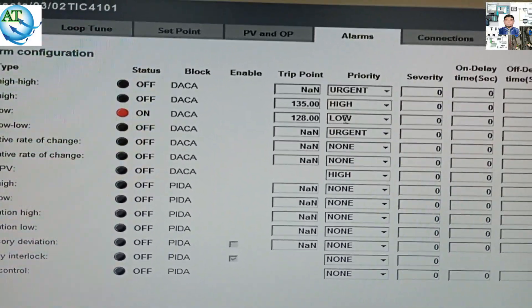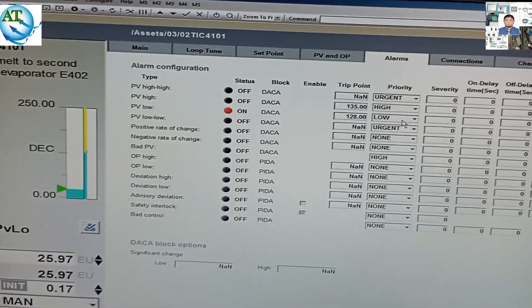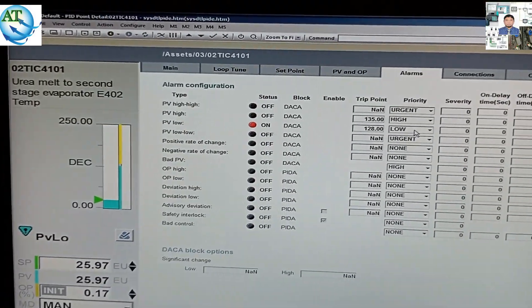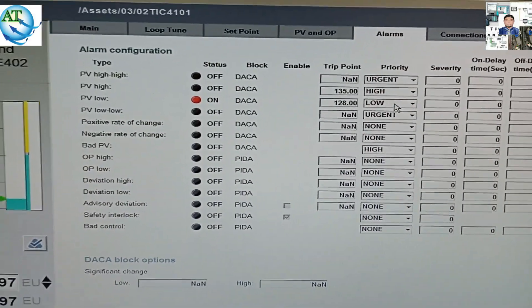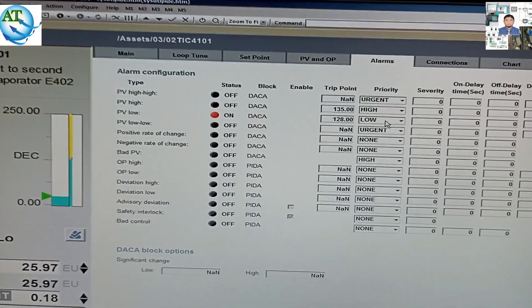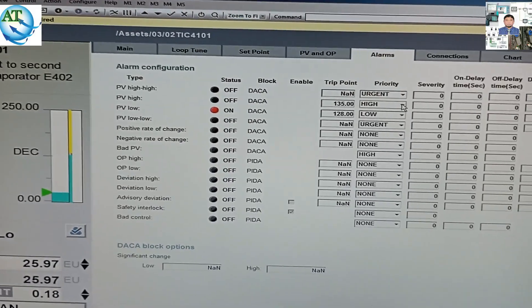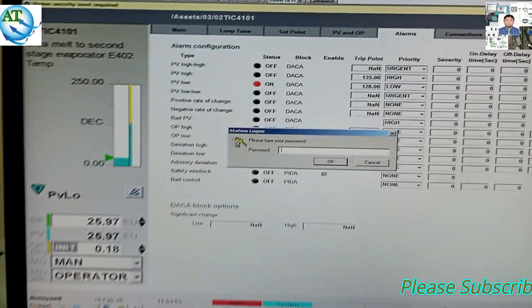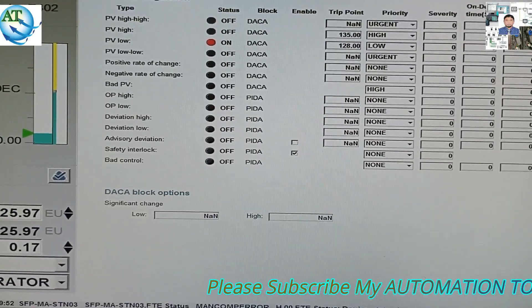First, you have to go to manager mode — you must be in manager mode. Without manager mode you cannot change anything. You can see the PV high setting priority is high and PV low setting priority is also low. I want to change both to urgent. I click on the login password, put in the manager password, and then we can log in and make changes.